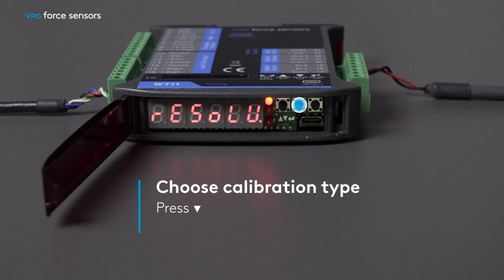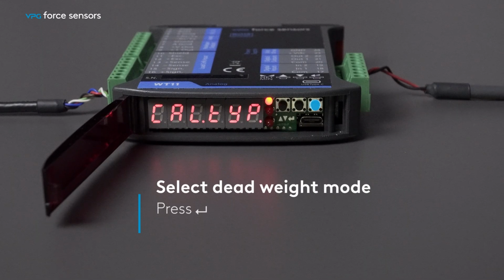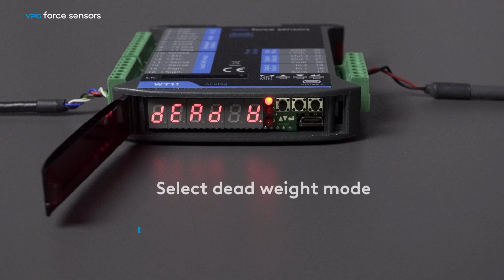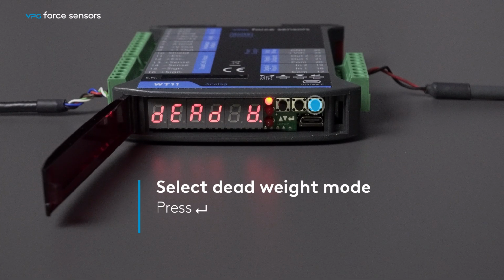Now, press the Down button and you will see Cal type appear on the screen. Press the Enter button so that the display shows Dead W. This indicates dead weight mode is selected. Press the Enter button to perform 0 and full-scale calibration.